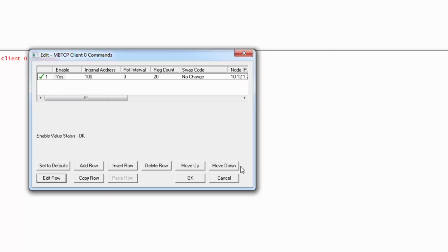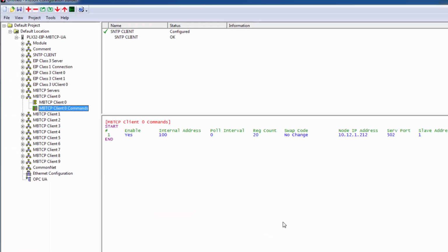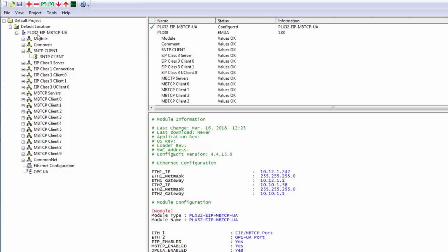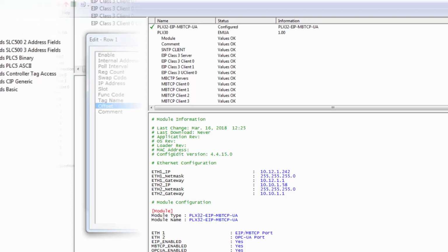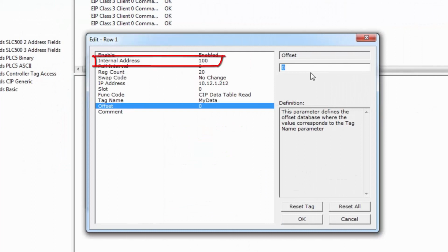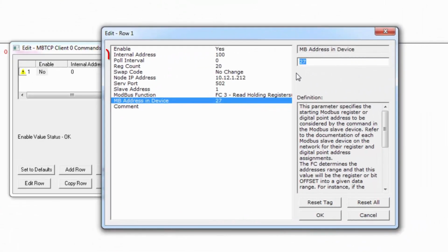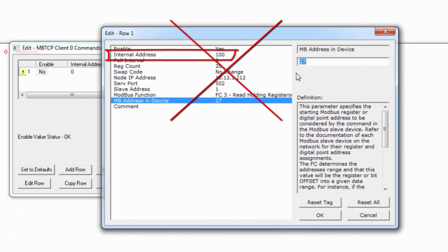We'll go back to our original configuration. You actually can share data with devices over Ethernet and Modbus TCP simultaneously through port 1. You just need to make sure that you're writing to different addresses in the gateway's database so as not to have data from one command overwriting data from another.